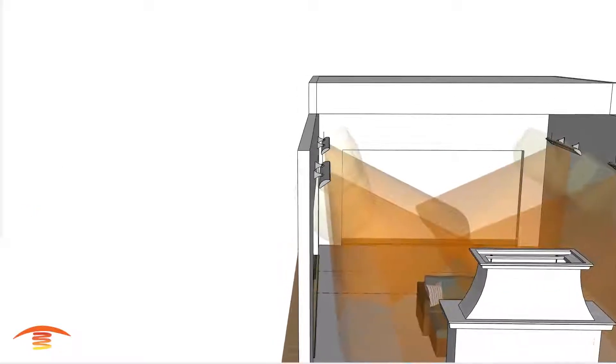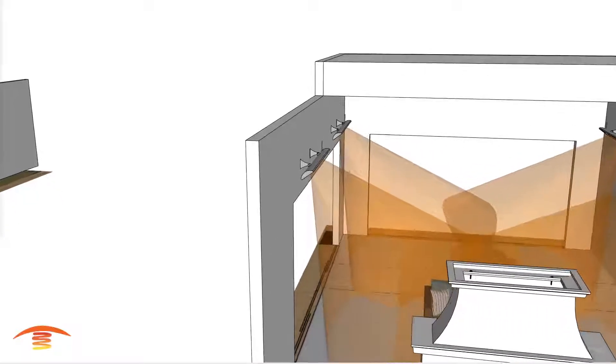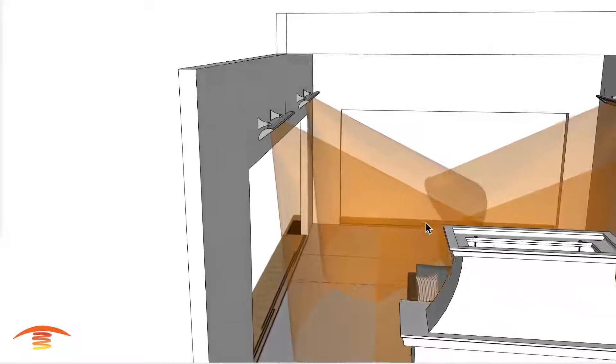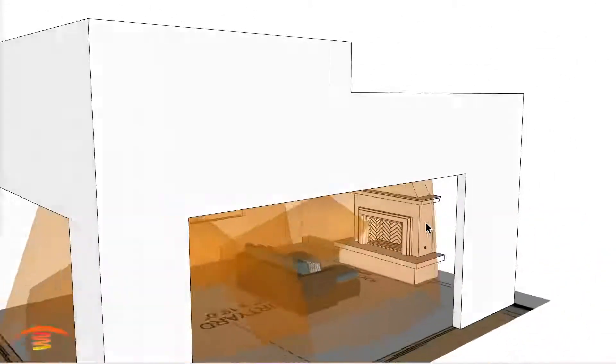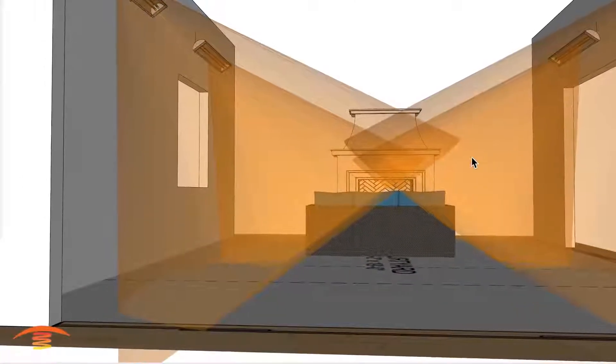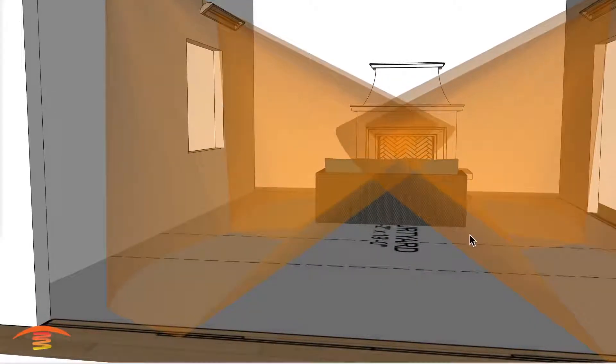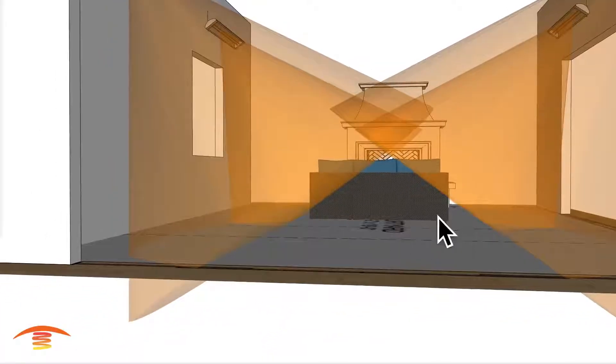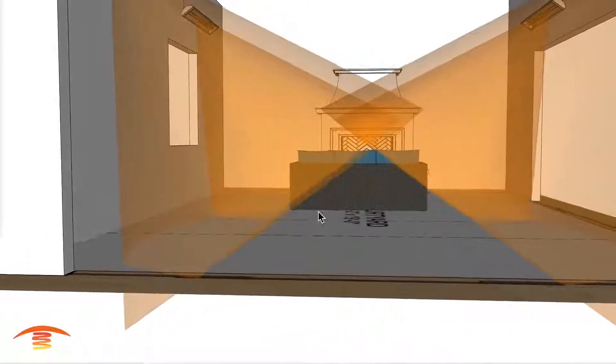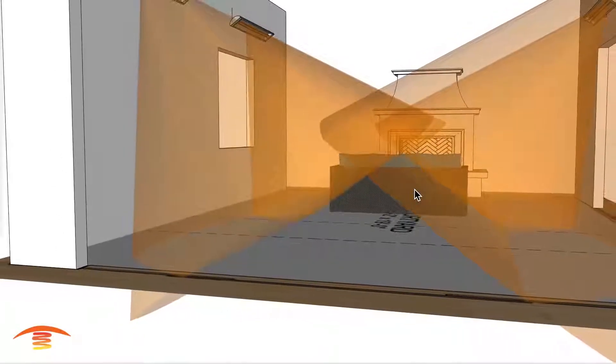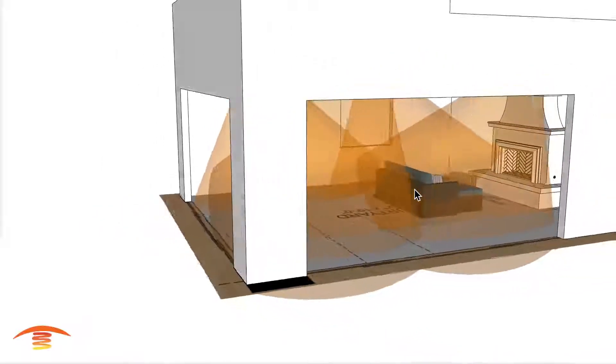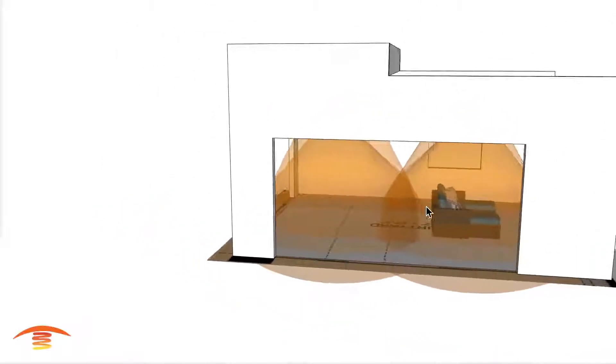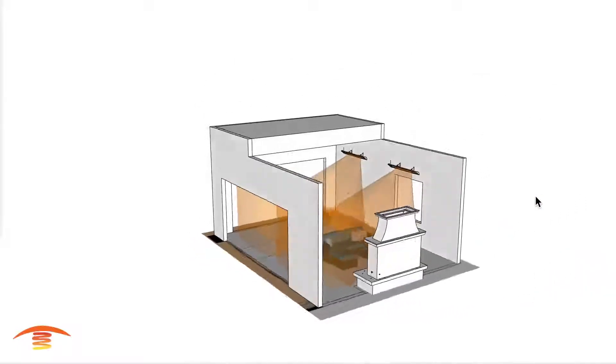Alright, let's look at the footprint of heat. You can see with this application here, I am at its furthest throw that's really available, but I'm getting overlapping rays. So that should make this space here, even though it's not highlighted here, it should make this space warm enough for comfort. This is Southern California. So I think that would be fine. And as far as the overall coverage here, we're getting pretty much all of the space out here.